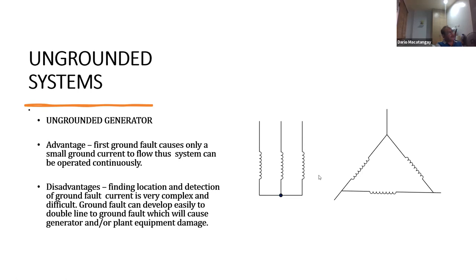The problem with an ungrounded system, and we do not normally use this, is the difficulty of finding that ground fault. It's very difficult because you would not know where to find it. Okay. That's the first type.